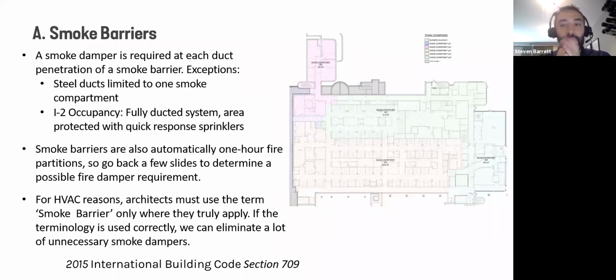So, this is going to seem pretty familiar. If you penetrate a smoke barrier, provide a smoke damper. There are some exceptions, some pretty strong and common exceptions. If your ducts are limited to one smoke compartment, then you do not need to provide a smoke damper at that smoke barrier. And in an I2, that's hospital occupancy, in a fully ducted system, and if the area has quick response sprinklers, you can omit the smoke damper when crossing that smoke barrier.